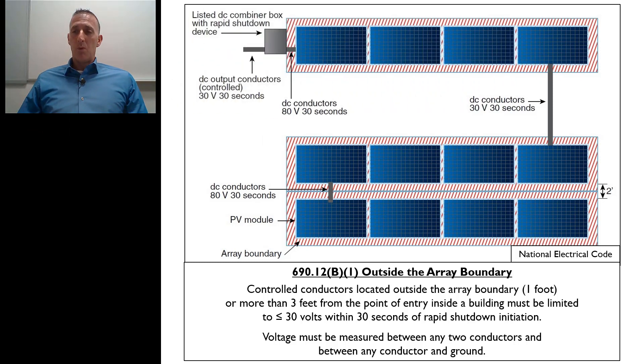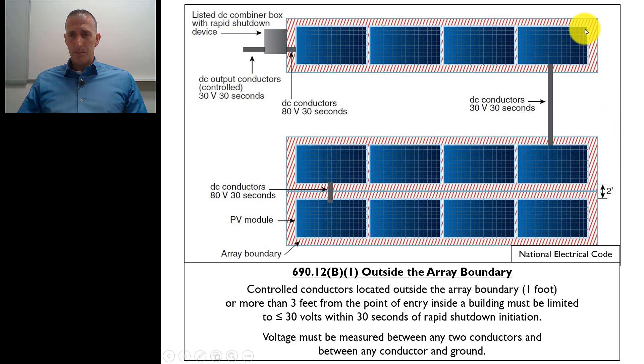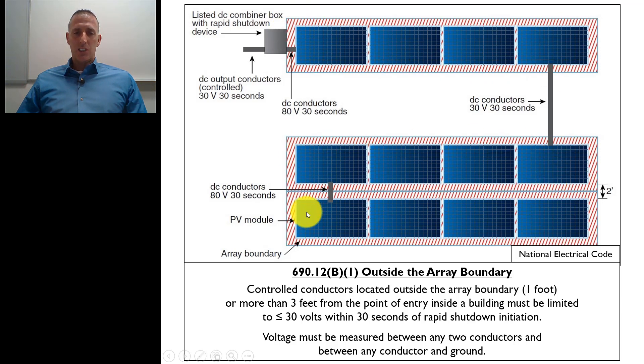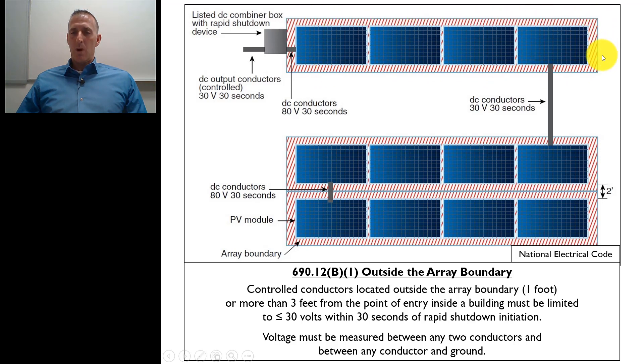In 690.12 B1 of the 2017 National Electrical Code, it goes into specific details about the conductors outside the array boundary. It states that controlled conductors located outside the array boundary — that one-foot boundary. If you take a look at this image, which is pulled from the 2017 National Electrical Code handbook, you can see the array outlined in blue, and the array boundary is one foot in each direction, outlined with those red hash marks.